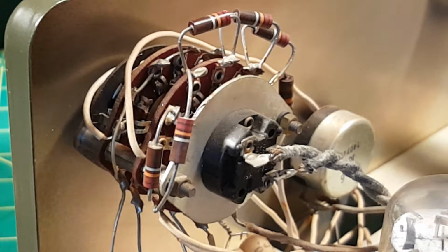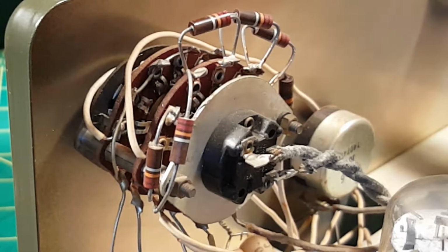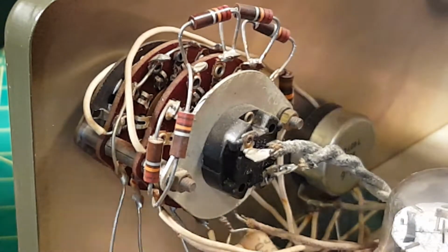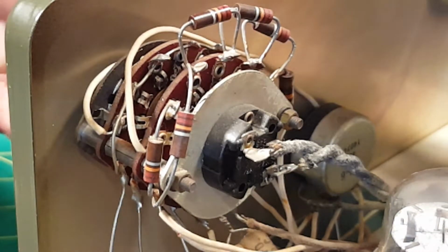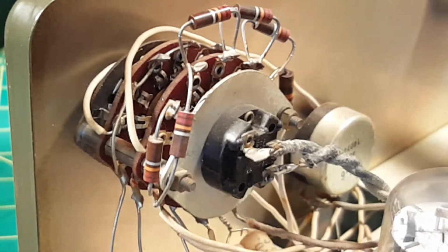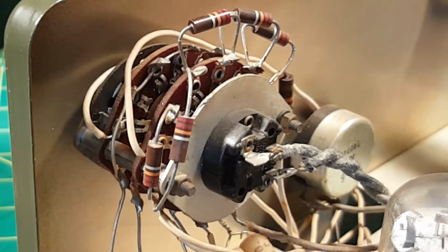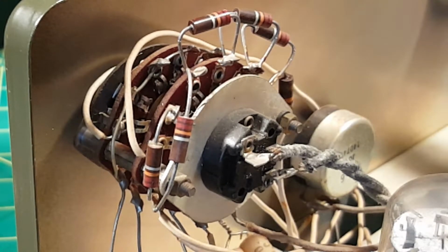So very cautiously at this time will I rotate the switch, looking at each contact as it comes into play. It should gently rise as the tab goes through the contact, and you should see the contact gently spread apart. If that doesn't happen, stop rotating the switch. If it does happen, continue on.